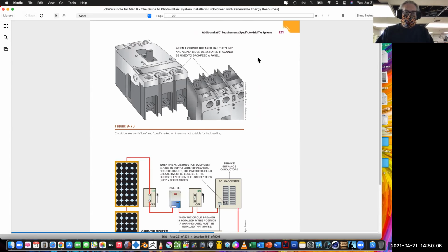When we look at our breakers, just remember the top of the breaker is where the power comes in, the bottom side is what comes out. That's line and load. But when we're talking about solar, which is which? My generation's coming from outside, and that's my line. My load is your house.